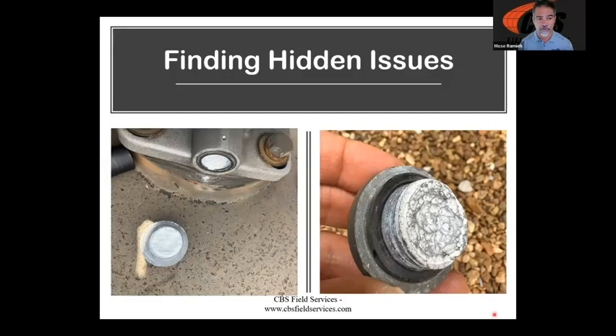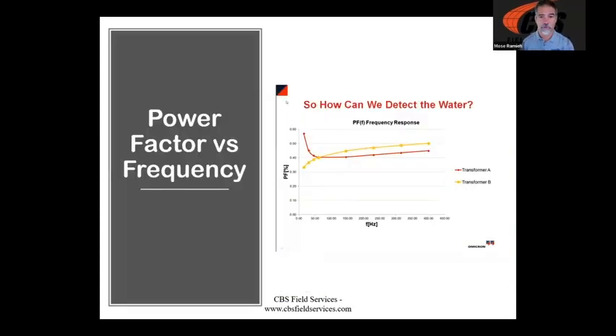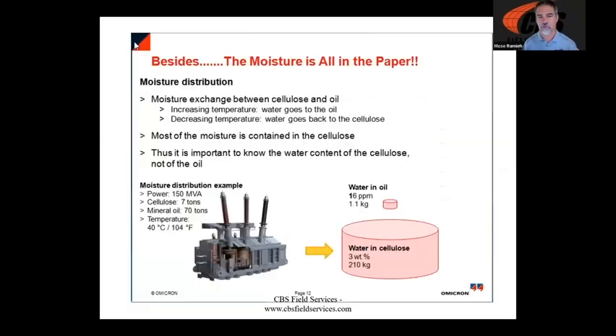Where before they might have seen that bushing fail down the road and never known why. So just some more notes about power factor testing. We can get the same kind of information about moisture in our transformer by, once again, testing over a variety of frequencies. And moisture in transformers, you could have a perfectly tight transformer, and just the natural aging of the paper materials that the transformer is made of will generate and create moisture in our oil.